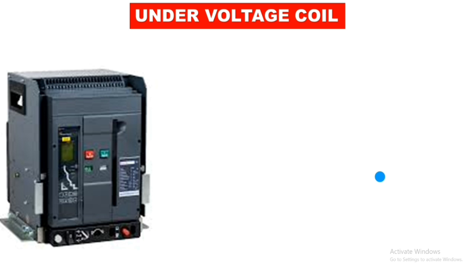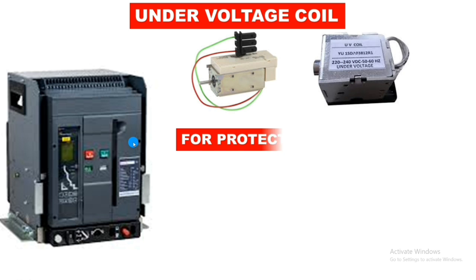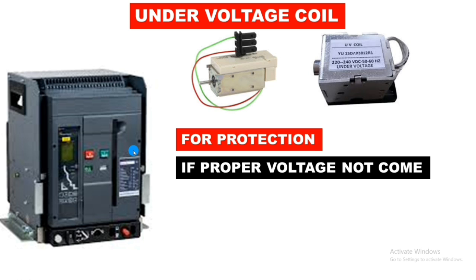The first coil is the under voltage coil — you can see the structure of this under voltage coil here. The under voltage coil may operate at 220 volt or 440 volt. You need to connect the under voltage coil for 440 volt because its main function is providing protection. If any phase is not coming into the ACB — due to a blown fuse or a substation fault — and proper voltage is not coming into the air circuit breaker, then this under voltage coil will trip the ACB.